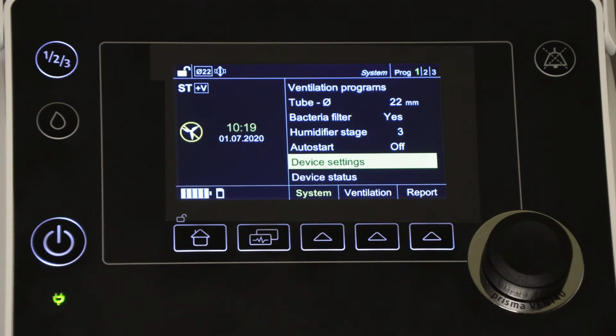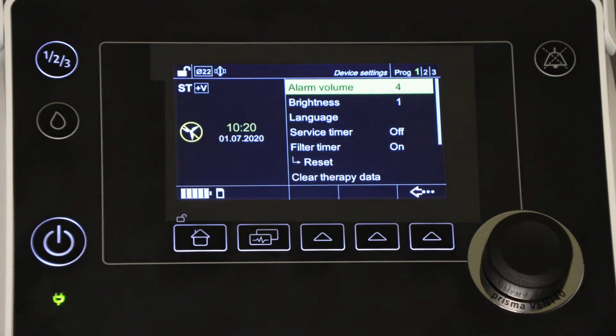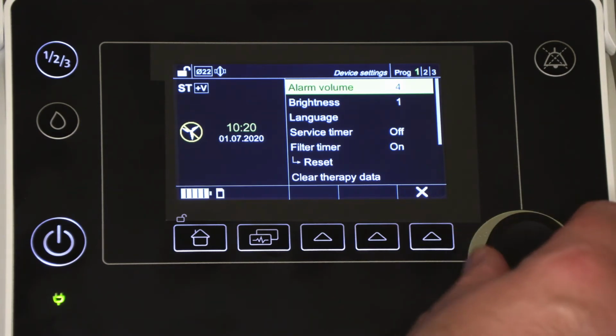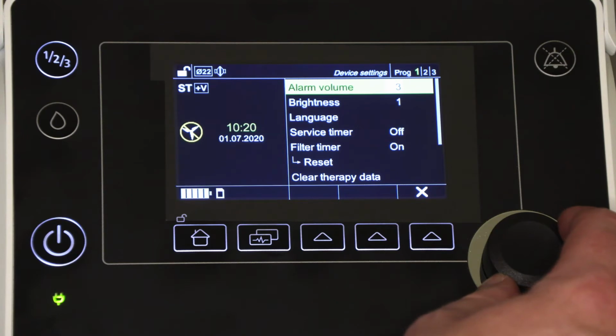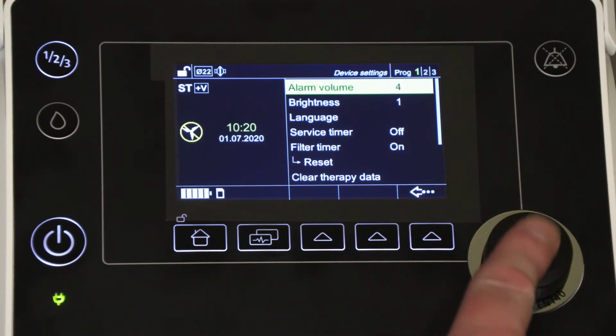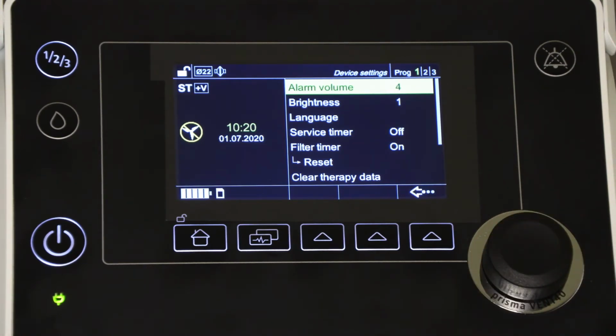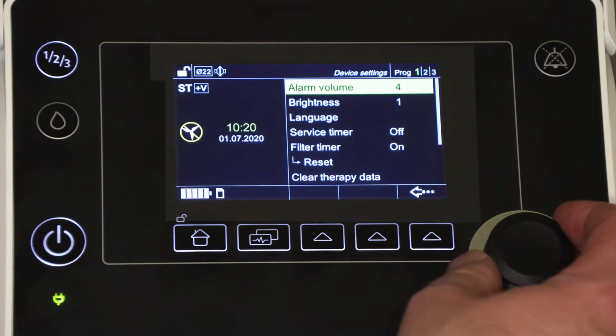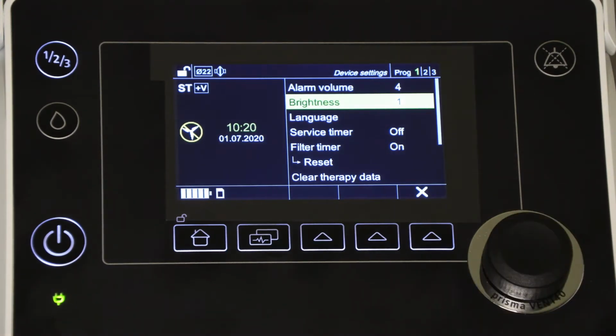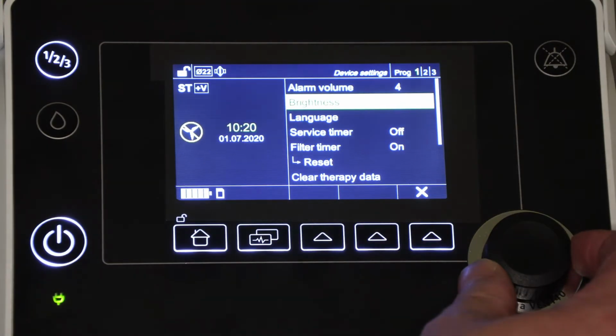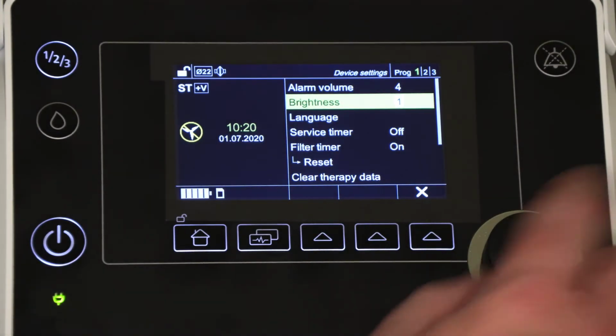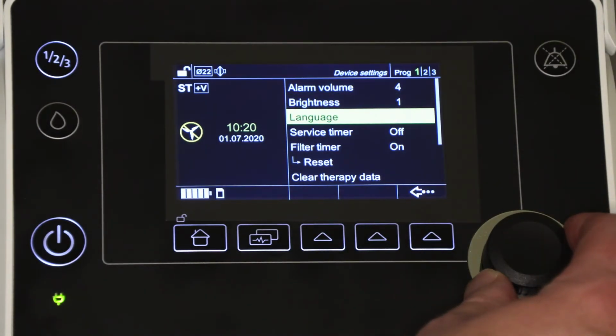Device Settings brings you into a separate menu called Device Settings. In this menu, you can adjust the volume of the audible alarm. Settings go from 1 to 4, and each time the setting is changed, an audible beep will sound, demonstrating how loud the alarm will be if left at that setting. The brightness will change the brightness of the screen between 3 stages. Here, the language setting on the device can also be changed.